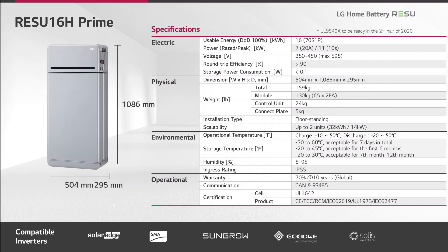The ingress rating is IP55, meaning this battery can be used inside or outside of the house. Inside the BMS, two protocols are represented: CANBUS and RS485 as communication protocols. This battery will be compatible with inverters from SolarEdge, SMA, and later also SunGrow, GoodWe, and Solis.